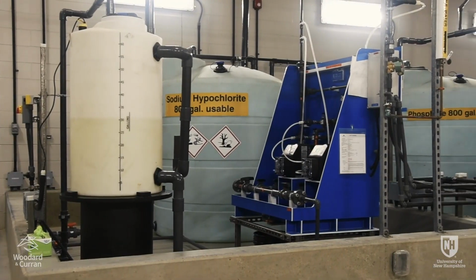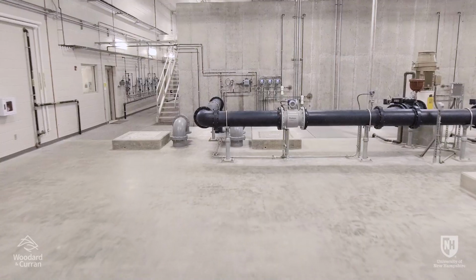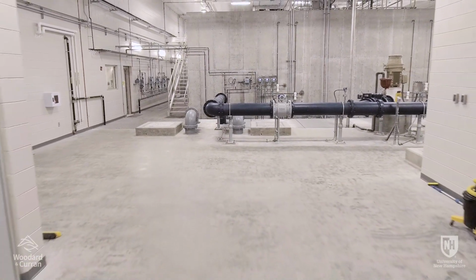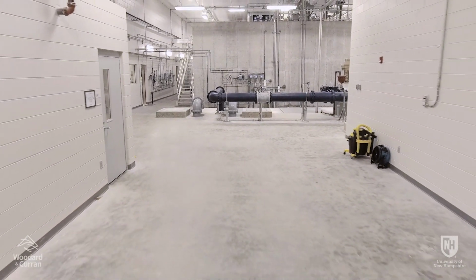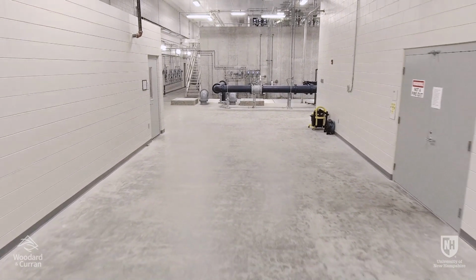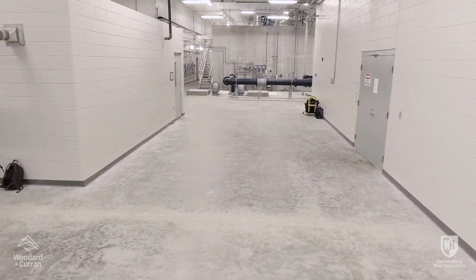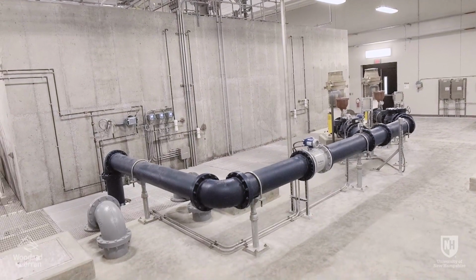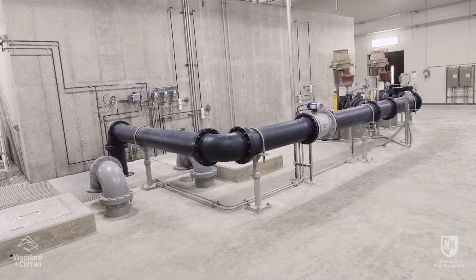After sufficient disinfection of the chlorine contact tanks, water flows into a series of clearwells. These tanks store water that is treated and ready for distribution. Over time, chlorine concentration decreases depending on water quality conditions. Operators ensure enough chlorine is added upstream of the chlorine contact tank so that not all of it reacts. The remaining residual disinfectant concentration reduces the growth of microorganisms in the distribution system.